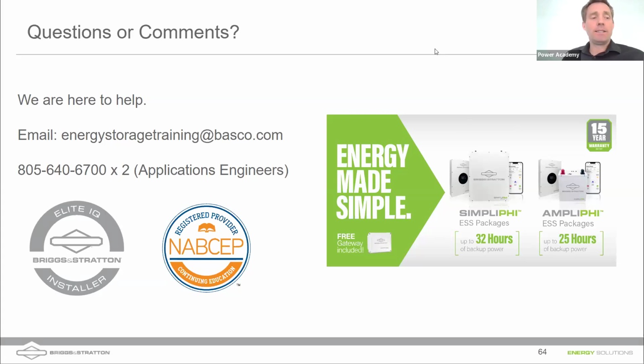The answer, unfortunately, is that because of the safety risks of opening up a battery, and the huge overall potential current there that could cause injury, we do not allow field replacement of our BMS units. However, I will say I never hear about our BMS units failing. It's a very rare occurrence if the BMS fails. If you're having problems with a battery, most likely it's another culprit. It doesn't mean the BMS can't fail, it's just not a common occurrence for us. The BMS units we put, especially in our AmpliPHI and SimpliPHI batteries, are Cadillac-designed BMSs that can probably handle a lot more power and current demands than we're currently putting on them. But the answer is no, sorry.